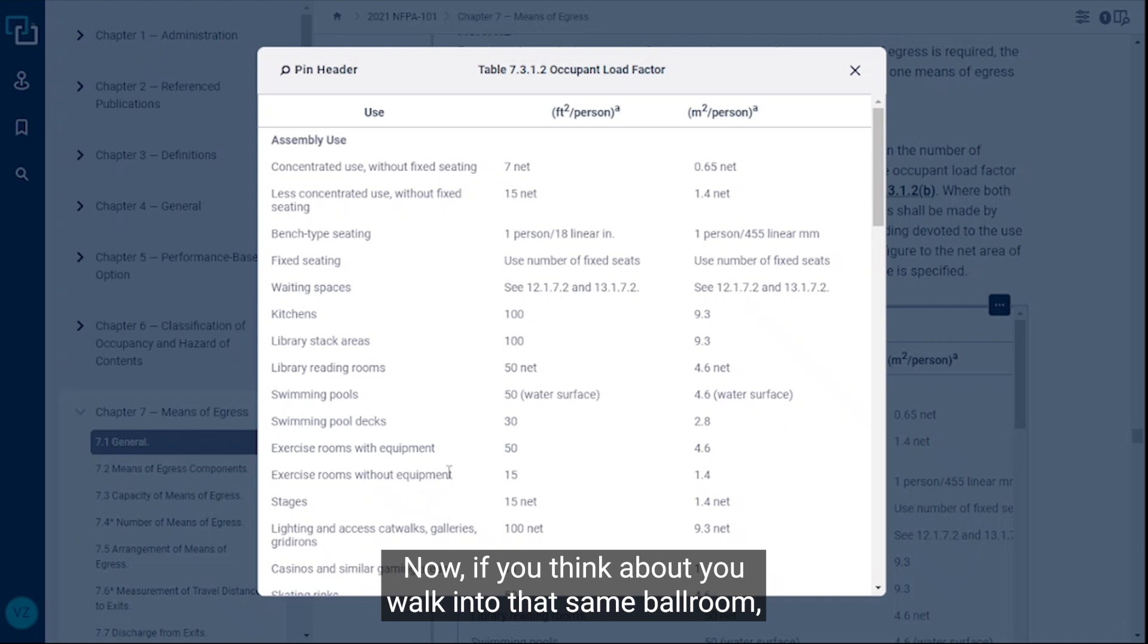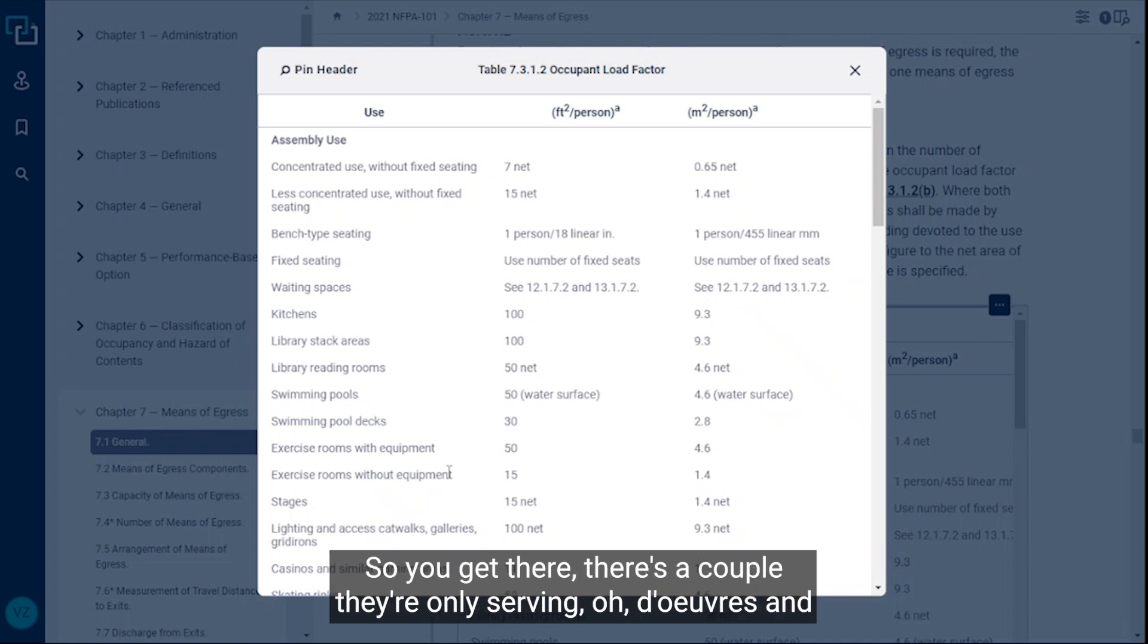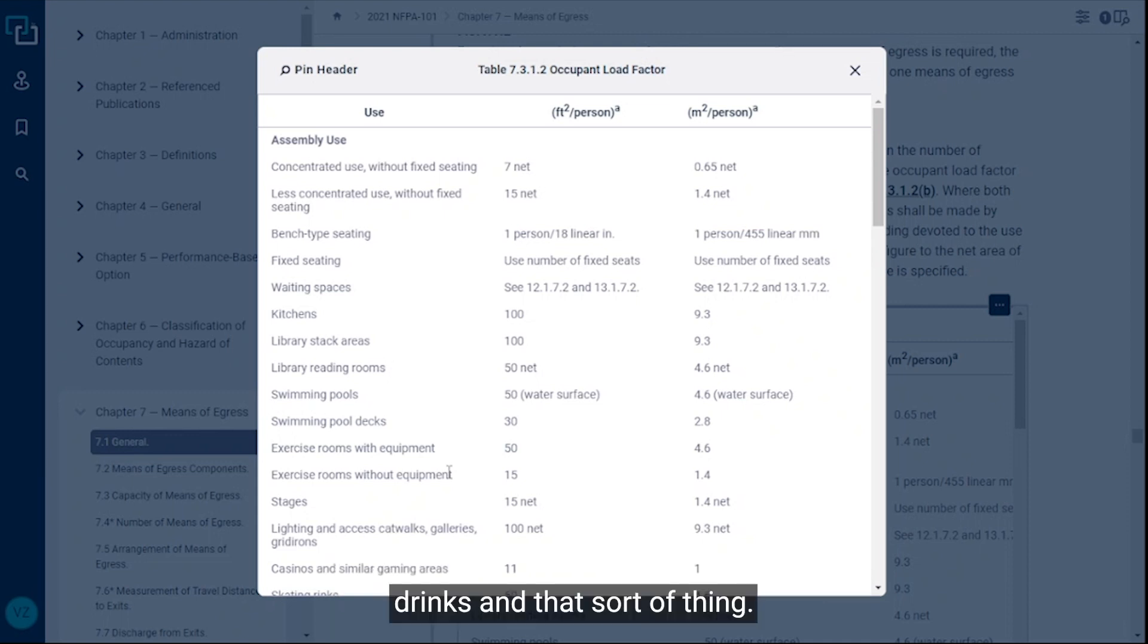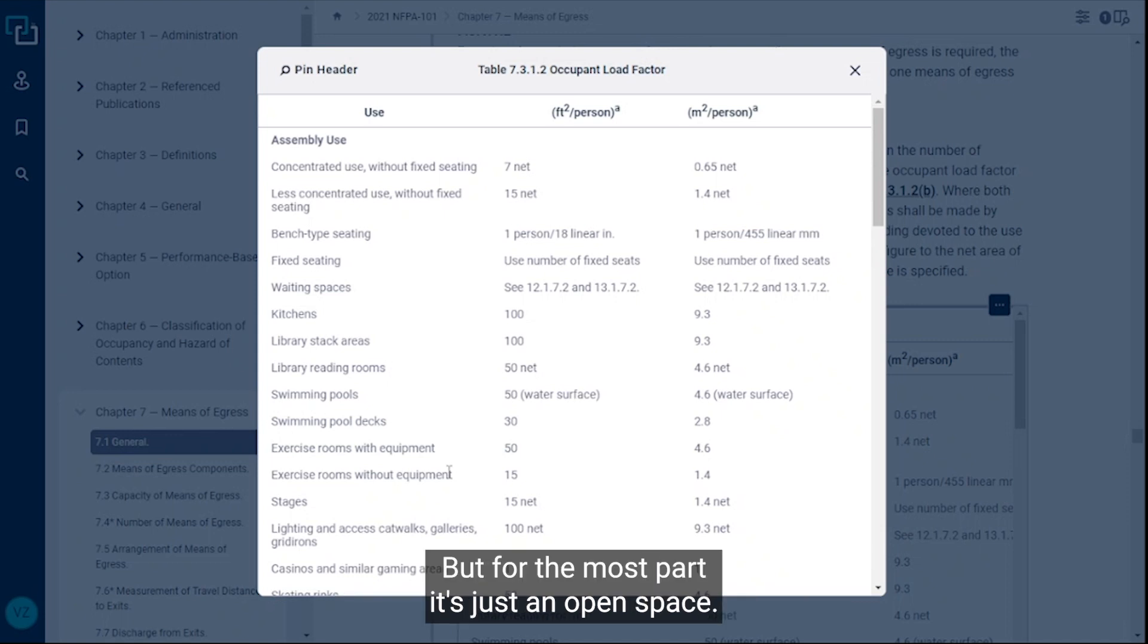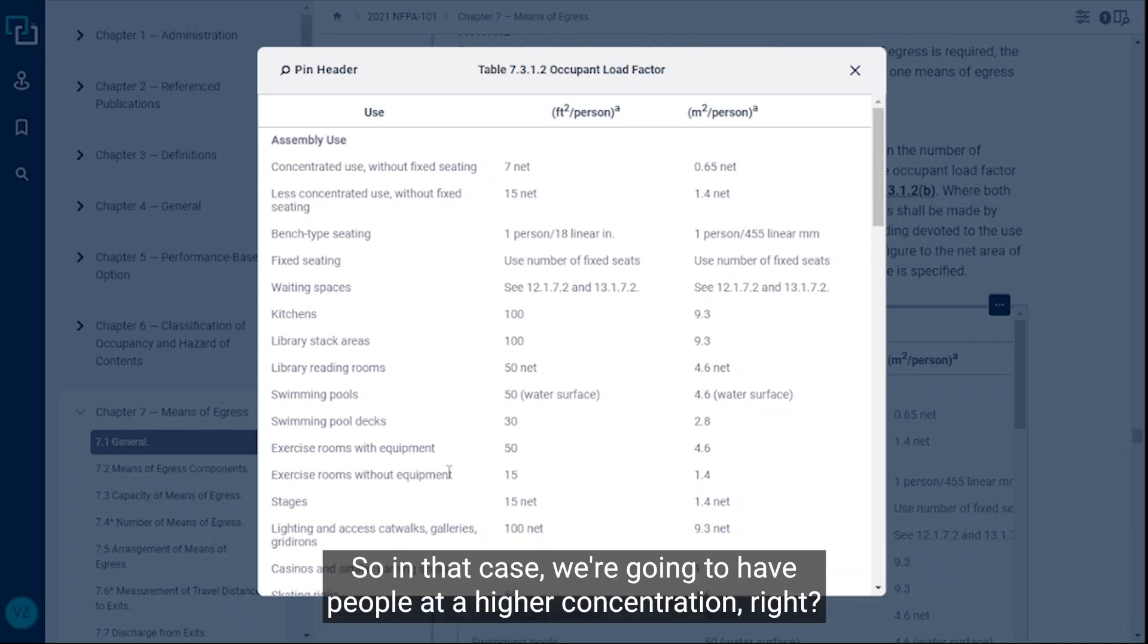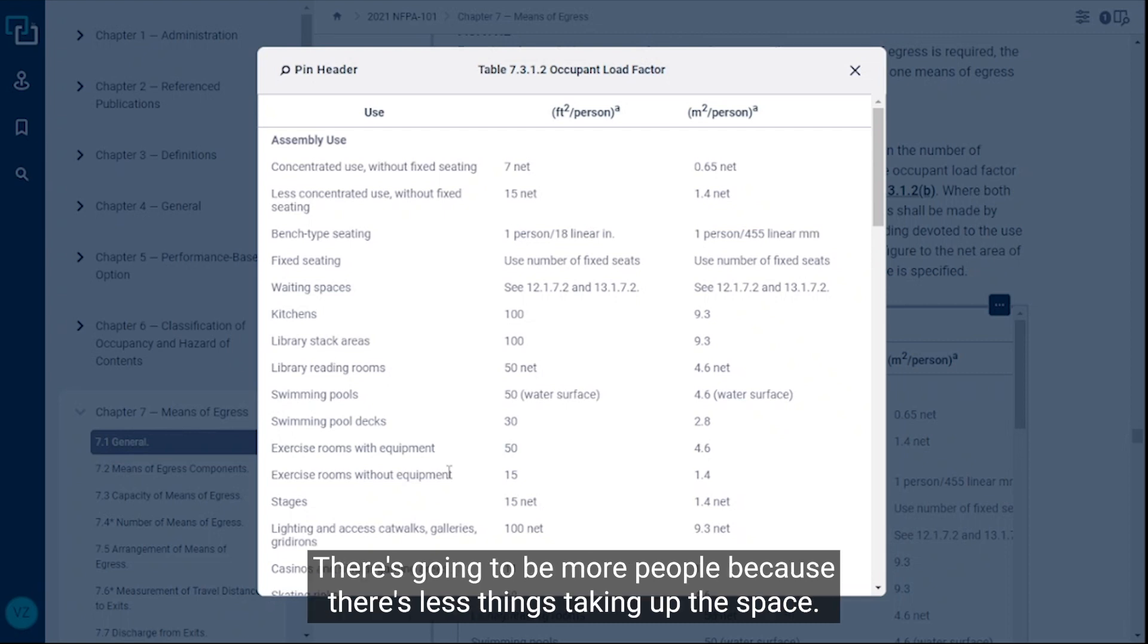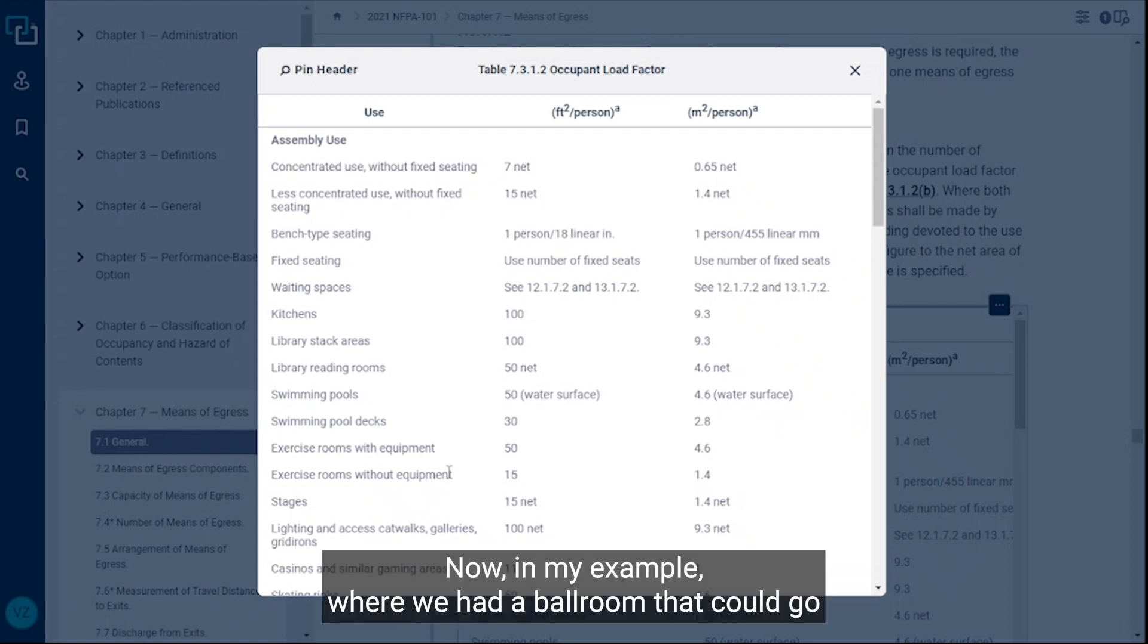Now if you think about, you walk into that same ballroom but it's late at night and it's for let's just say a function. You get there, they're only serving hors d'oeuvres and drinks and that sort of thing, so there's a couple of high top tables but for the most part it's just an open space. In that case we're going to have people at a higher concentration. There's going to be more people because there's less things taking up the space. That's an example of where you would use the concentrated use.